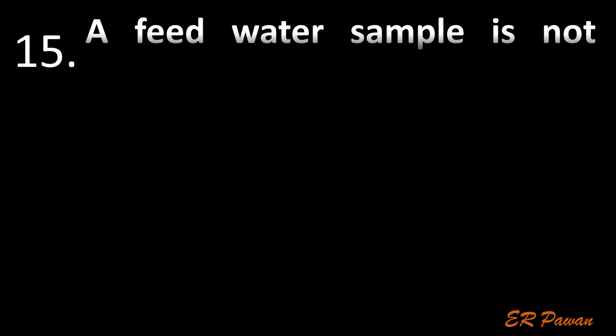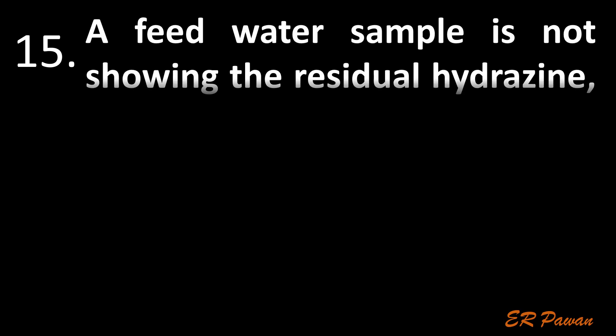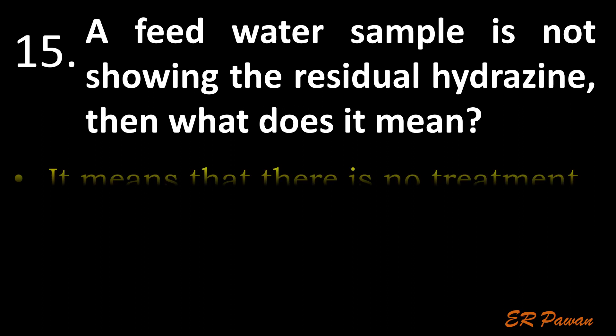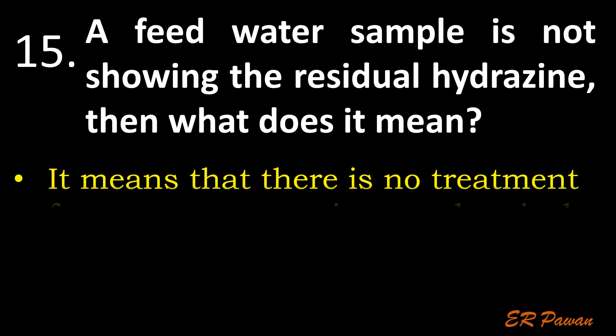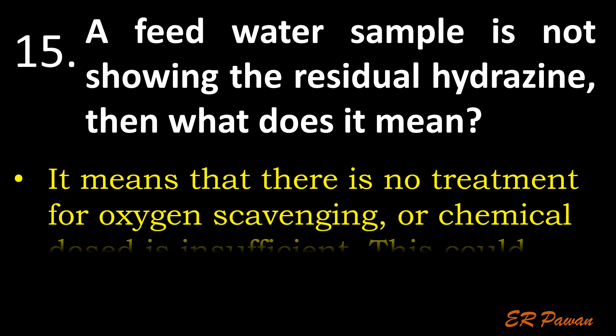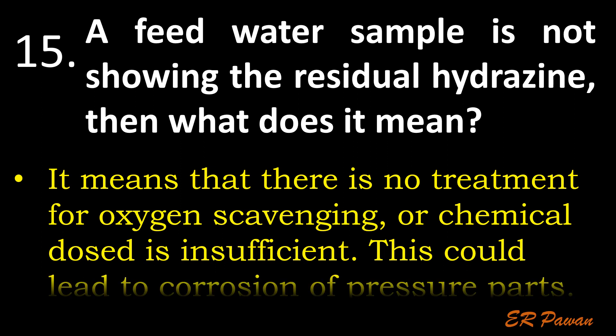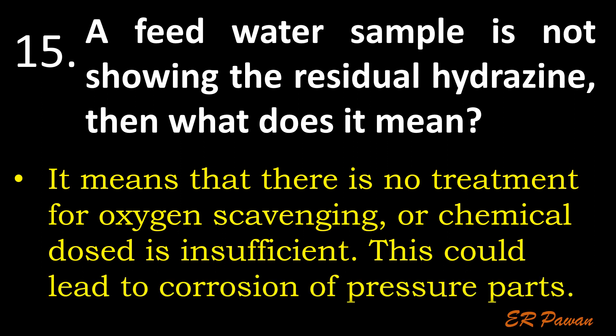Question 15: A feed water sample is not showing residual hydrazine — what does it mean? It means that there is no treatment for oxygen scavenging, or the chemical dose is insufficient. This could lead to corrosion of pressure parts.